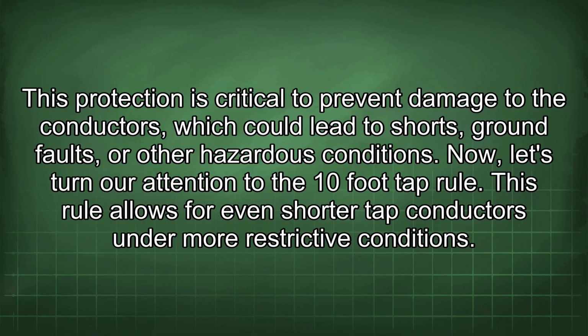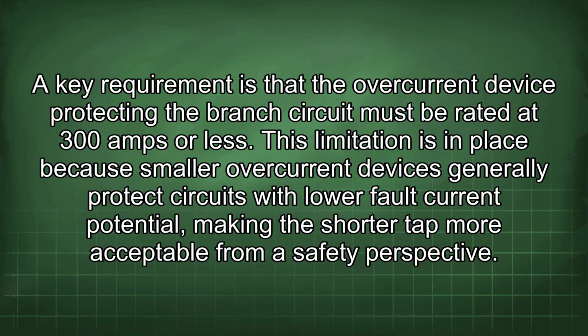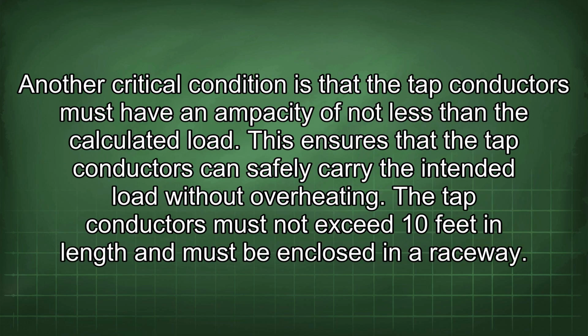This rule allows for even shorter tap conductors under more restrictive conditions. A key requirement is that the overcurrent device protecting the branch circuit must be rated at 300 amps or less. This limitation is in place because smaller overcurrent devices generally protect circuits with lower fault current potential, making the shorter tap more acceptable from a safety perspective. Another critical condition is that the tap conductors must have an ampacity of not less than the calculated load. This ensures that the tap conductors can safely carry the intended load without overheating.